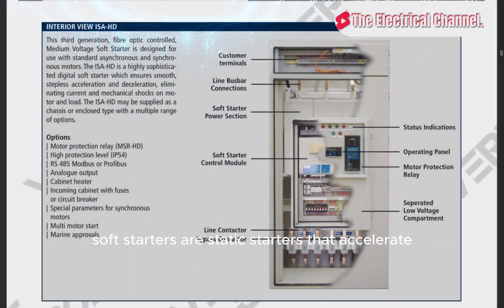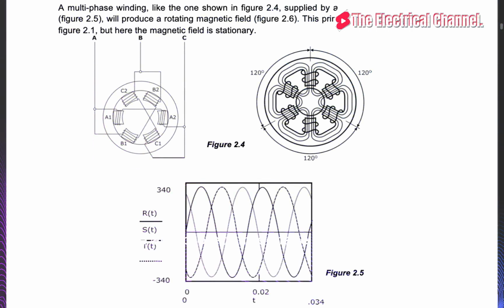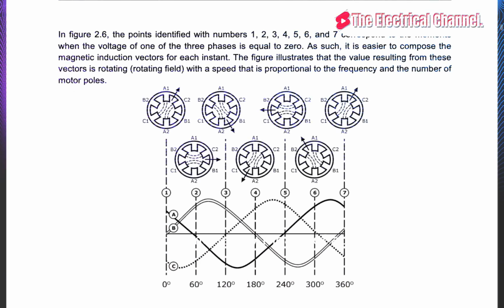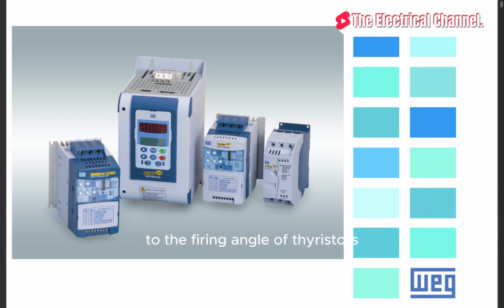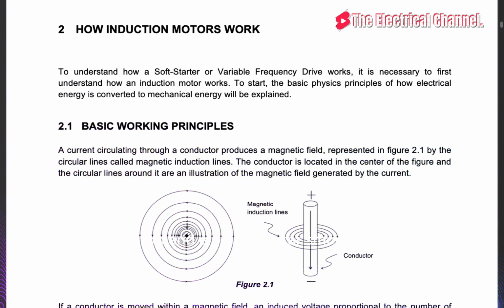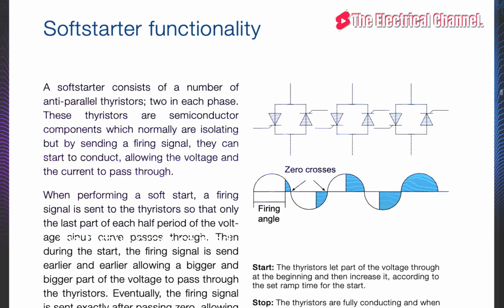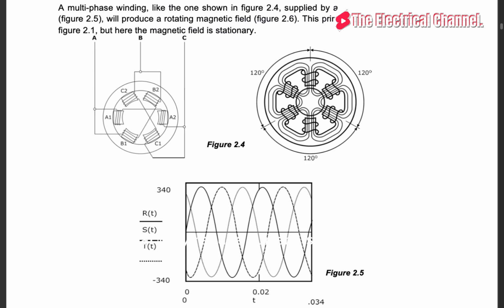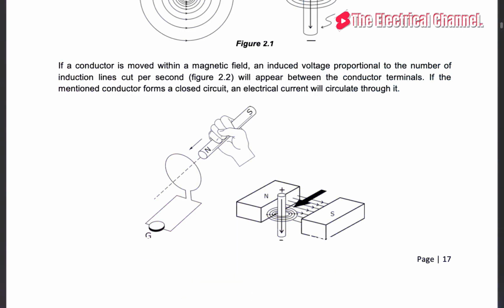Soft starters are static starters that accelerate, decelerate, and protect three-phase induction motors. The control of the voltage applied to the motor by means of adjustments to the firing angle of thyristors allows the soft starter to start and stop an electric motor smoothly. With adequate adjustments of variables, the torque produced is adjusted to the needs of the load, so that the required current is going to be the lowest possible for the starting procedure.